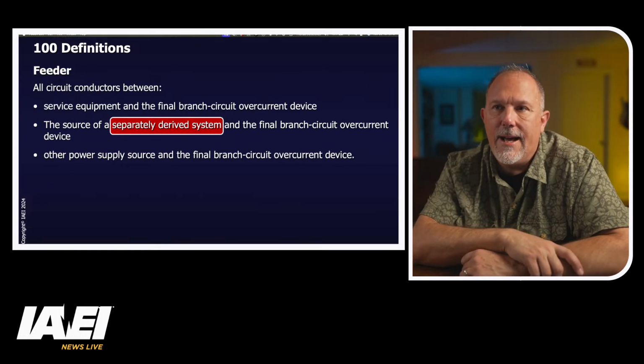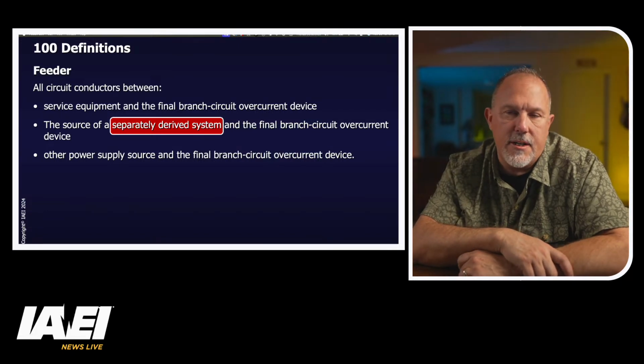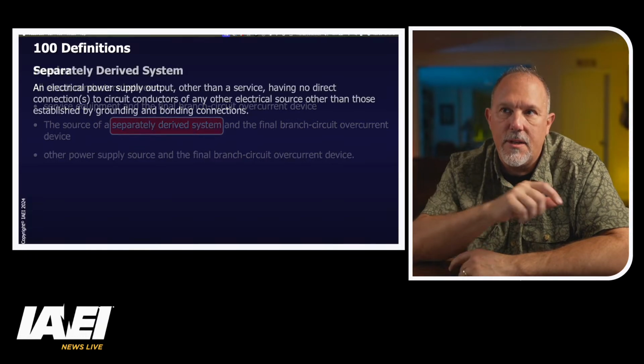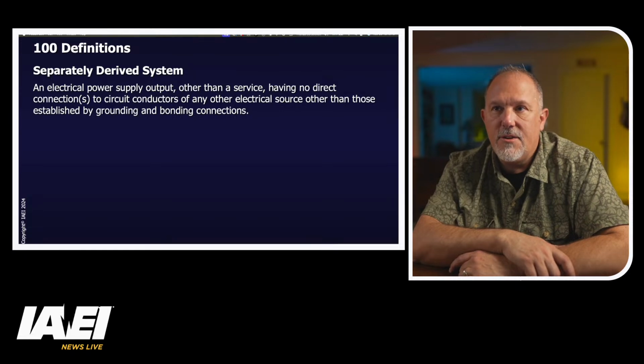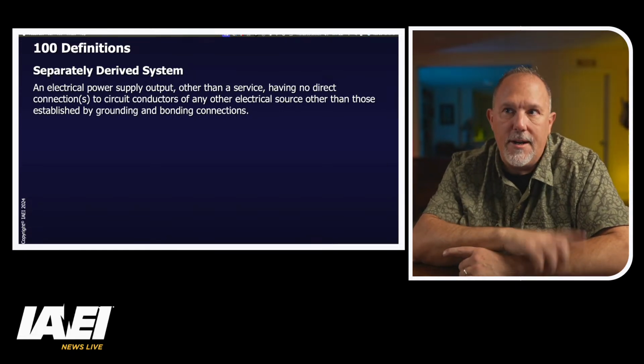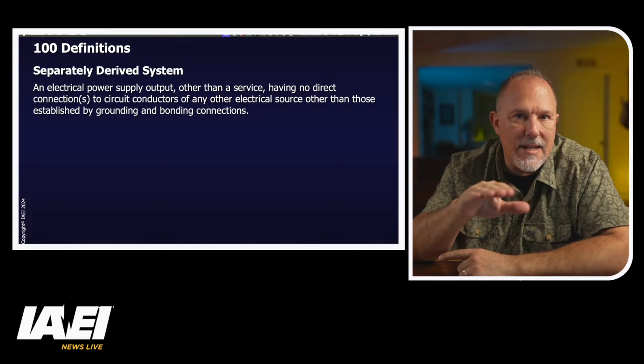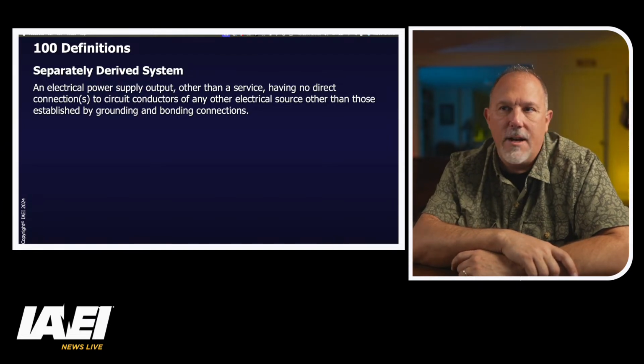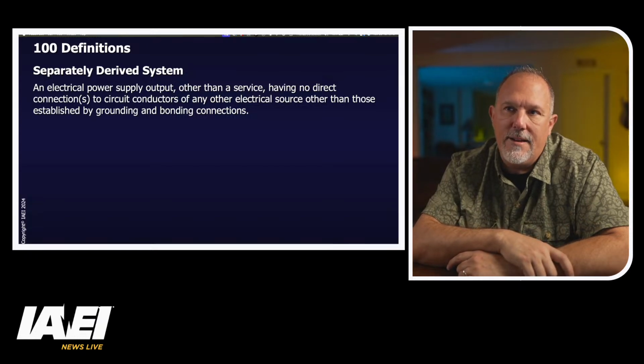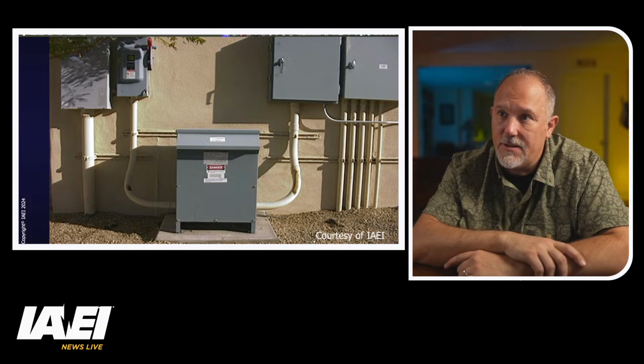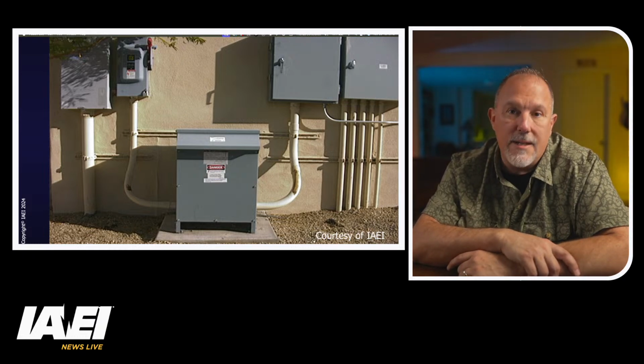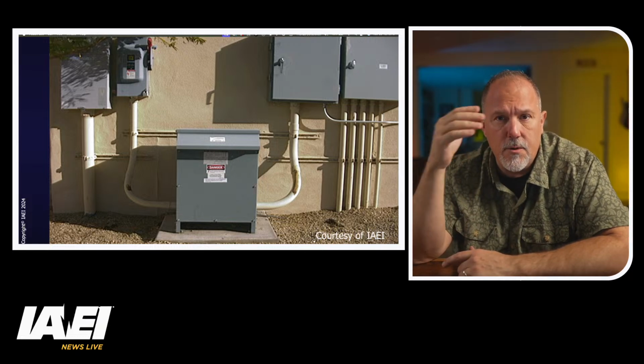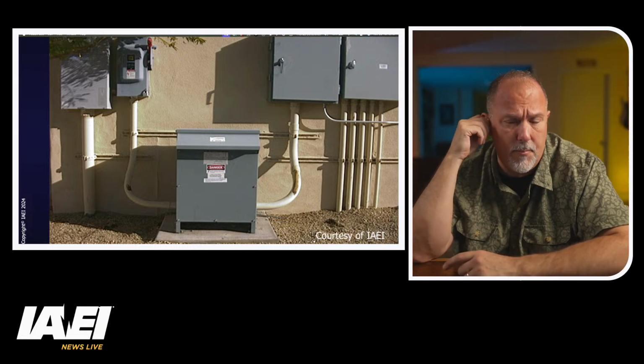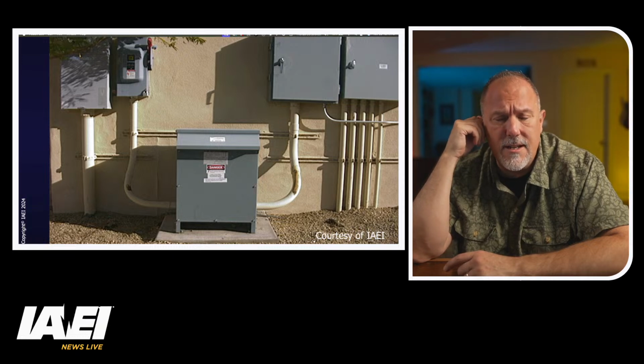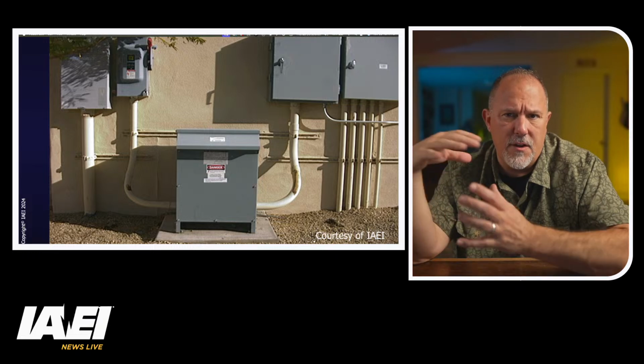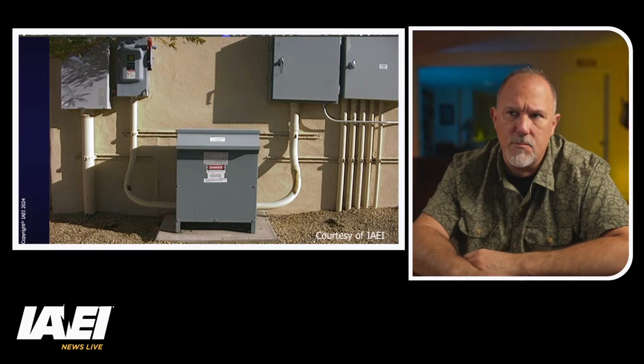All right? Now, in the definition of a feeder, it says all circuit conductors between the source of a separately derived system. Well, what's a separately derived system? It's a defined term. A separately derived system is an electric power supply output other than a service. It has no direct connection to circuit conductors of any other electric service, any other electrical source other than the bonding. So here's an example. Transformer. A delta Y ground transformer, now an autotransformer has common windings between line and load. That would not be a separately derived source. Delta, delta, delta Y ground, delta Y, Y, Y, all of those different configurations where the cores are separate, those are all separately derived systems.